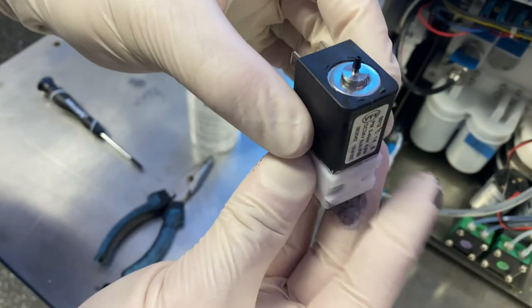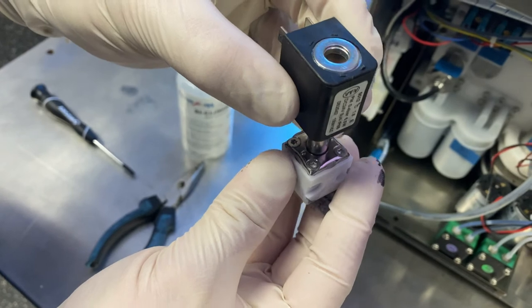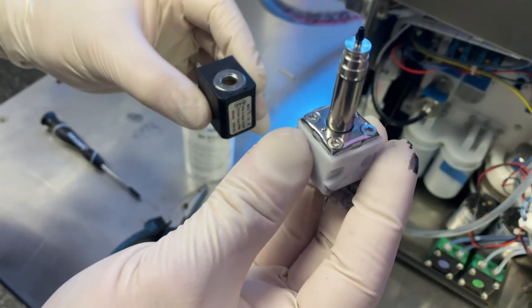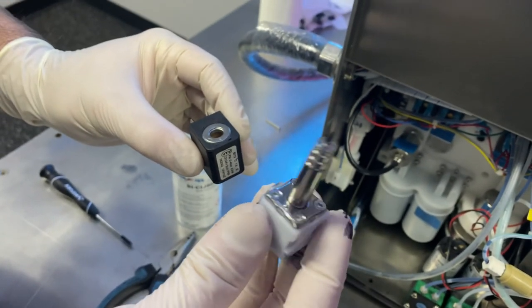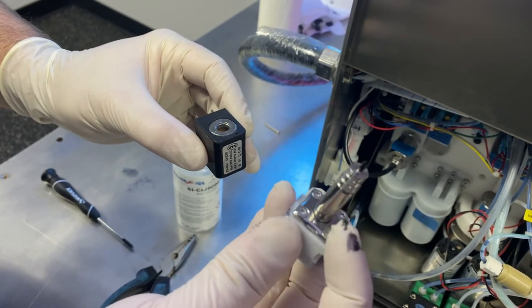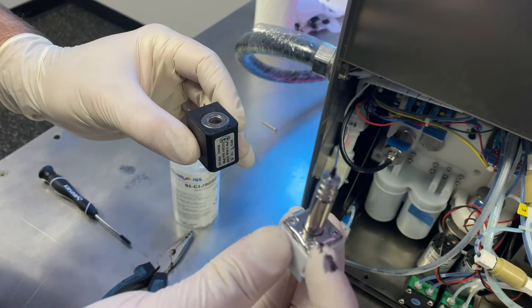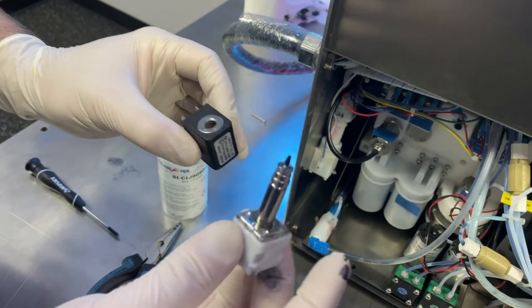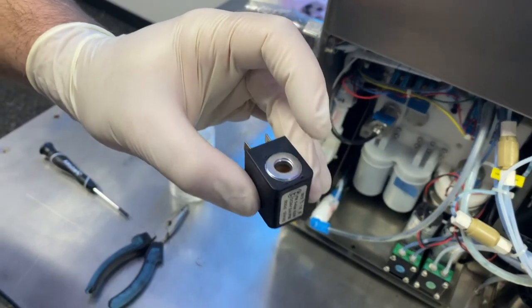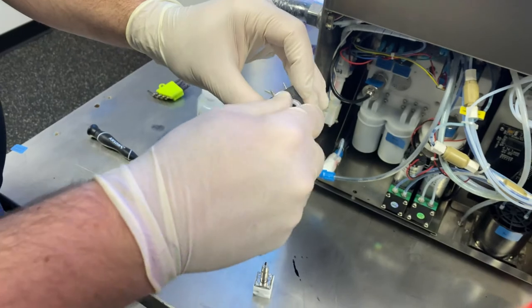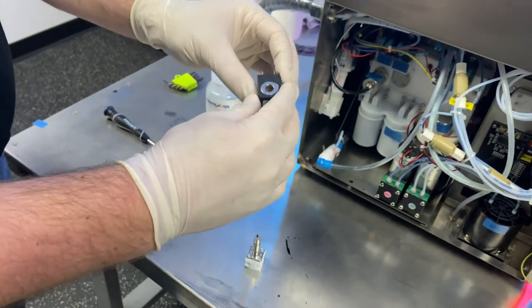With the clip off, we can slide the plunger housing out of the solenoid. This is what we want to get at - this is where the moving parts are, and this is what could potentially be seized up. So we're going to set the solenoid off to the side. Be aware again of this flat washer, and make sure you don't lose that.